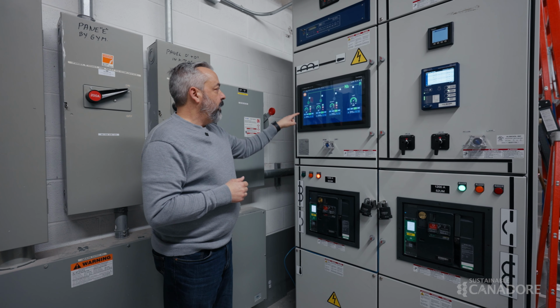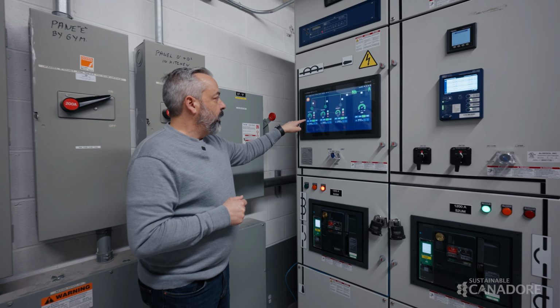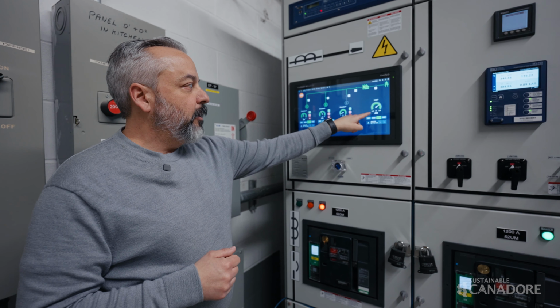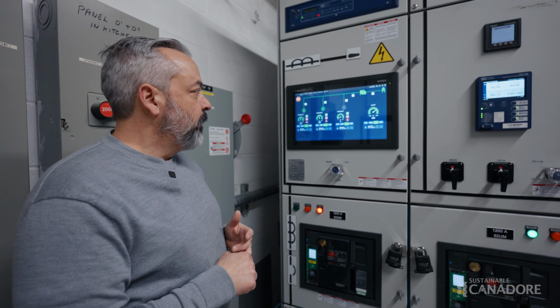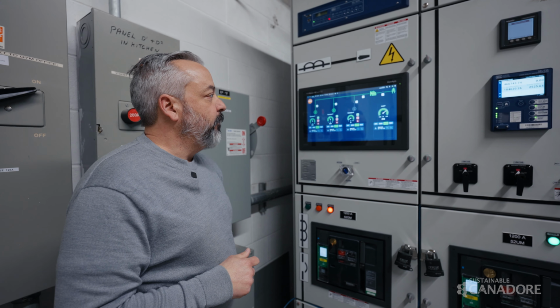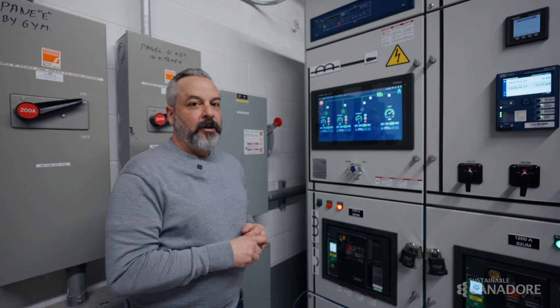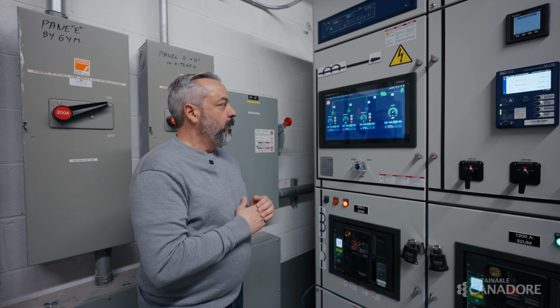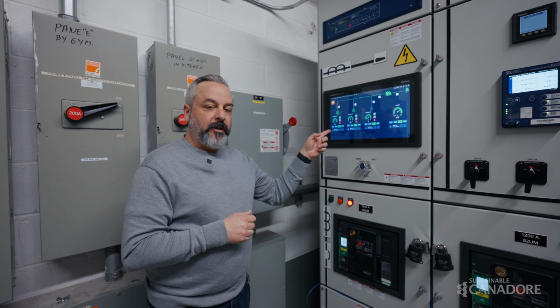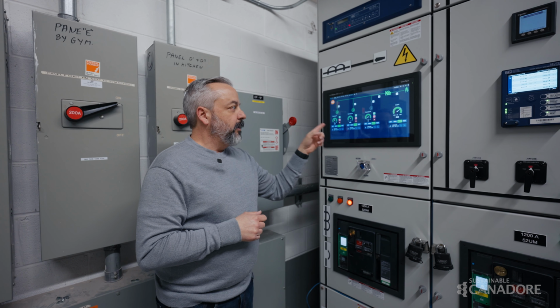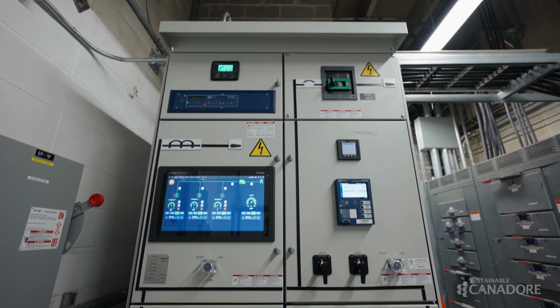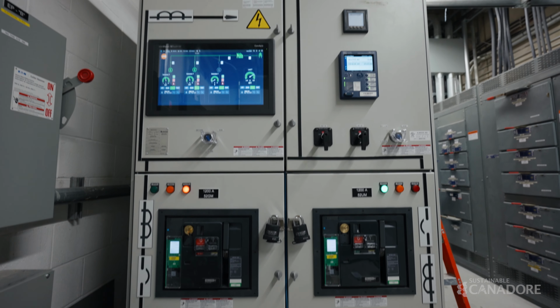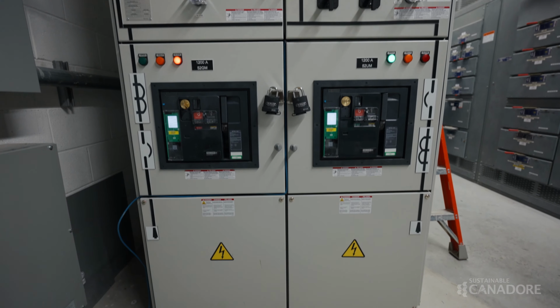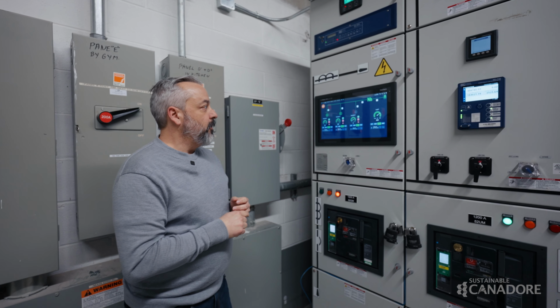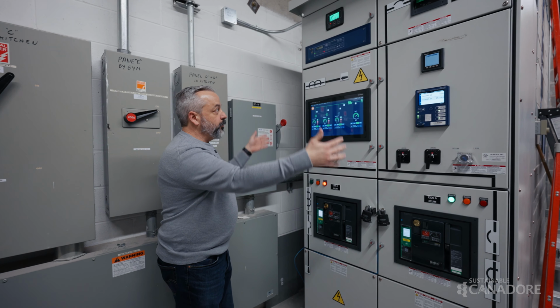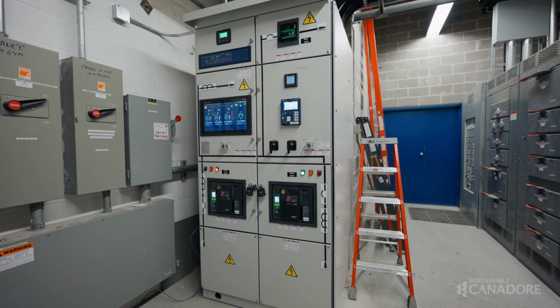So you can see we have two generators working at about half capacity. We could go all the way up to a megawatt of power, and right now we're using about half of what we can actually produce on site. So we could scale up, scale down, identify what's using power, shut things off, and really just control exactly what we're using on site. This is physically connected to the Cogen and to the dome, and it's all controlled via this motor control center right here.